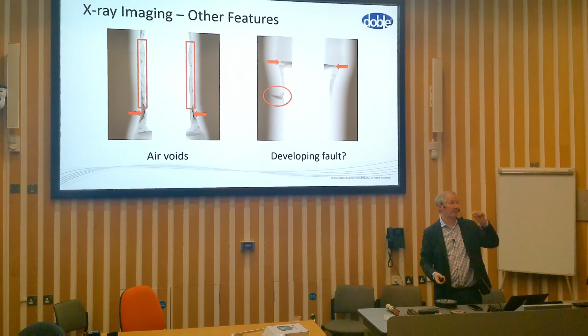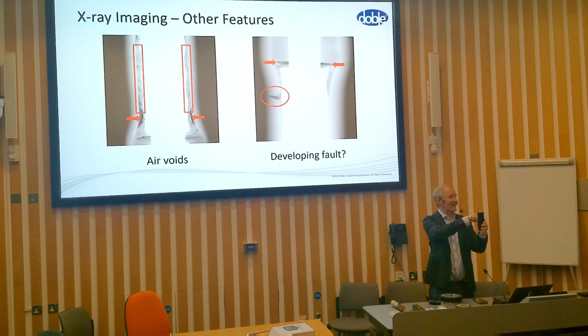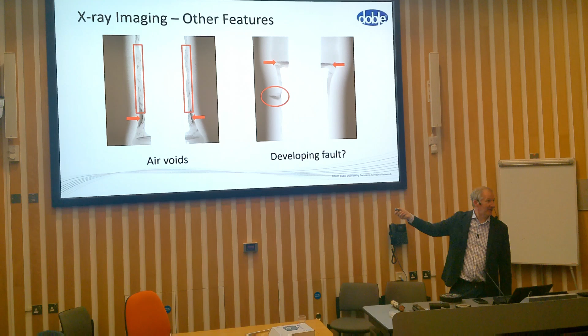We also saw another developing fault in one of the other joints. Because the joint was done carefully, each cable was X-rayed 3 times, 120 degrees apart, since anything on one side of the conductor won't be visible from a single angle. Doing it 3 times gives full visibility, so we knew the orientation. That meant later, when we cut it open, I could avoid damaging things because I knew exactly where they were in the joint.